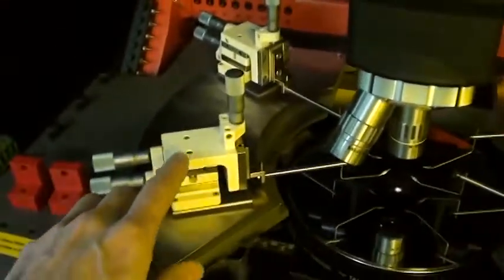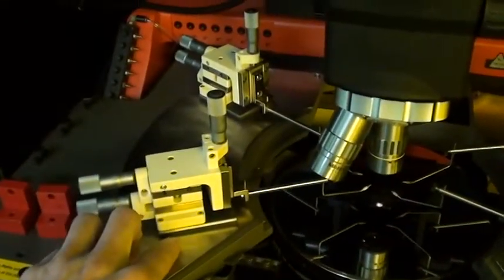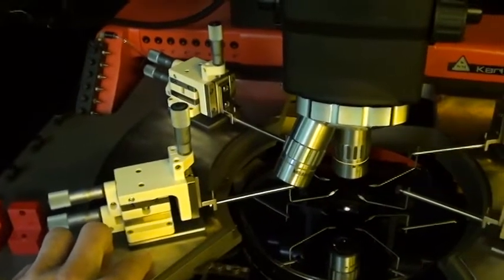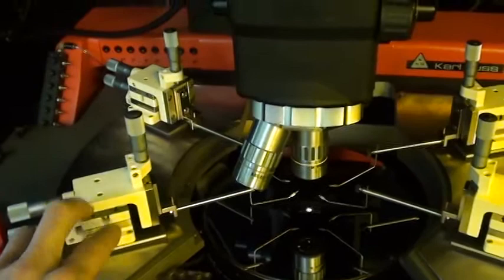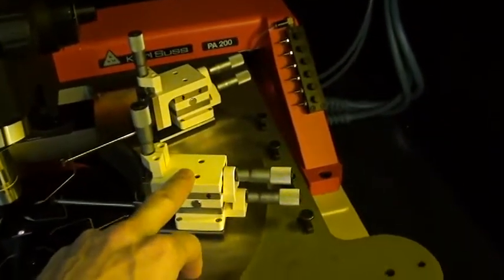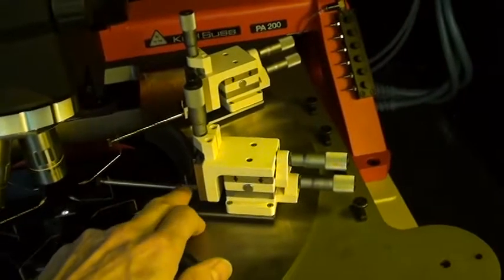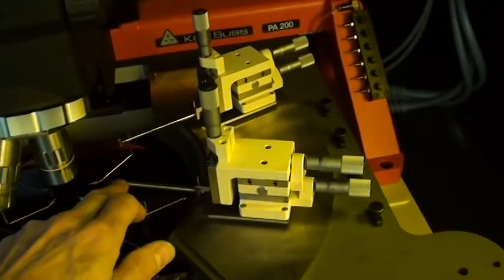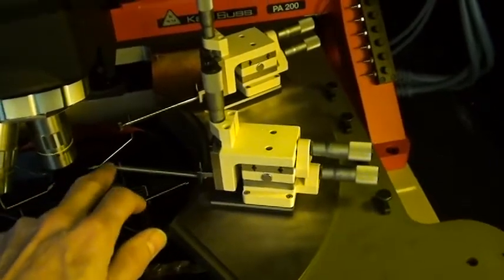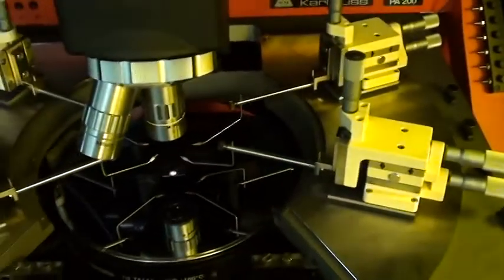These particular positioners were not appropriate for this type of a platen this large. So what we often do in this situation is use these little R&K type positioners. We have these little extensions made right here, and by the bracket assemblies and the probe arm. And so as you can see, that works pretty well.